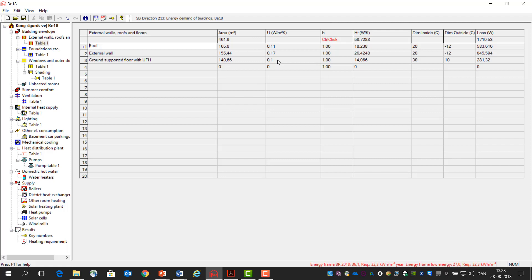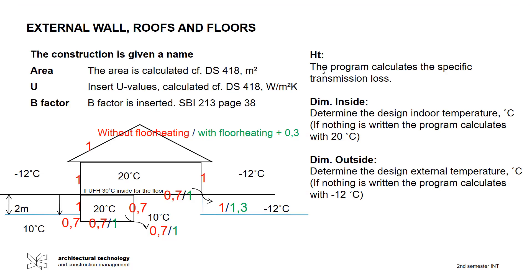Then we have the B-factor, and the B-factor is the temperature factor according to which temperatures we have. Normally when we have 20 degrees inside and minus 12 degrees outside, it's 1. I will also put it up in the guideline that you have for BE18, and you can see here the red ones is without underfloor heating, so that's when we have 20 degrees and minus 12 outside.